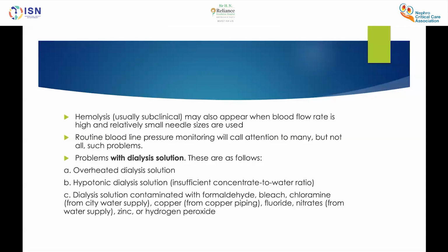There can be a problem with the dialysis solution, that is overheated dialysis solution, hypotonic dialysis solution, or dialysis solution that's contaminated with formaldehyde, bleach, chloramine, which could be from the city water supply, or from piping contaminated with copper, fluorides or nitrates, zinc or hydrogen peroxide.